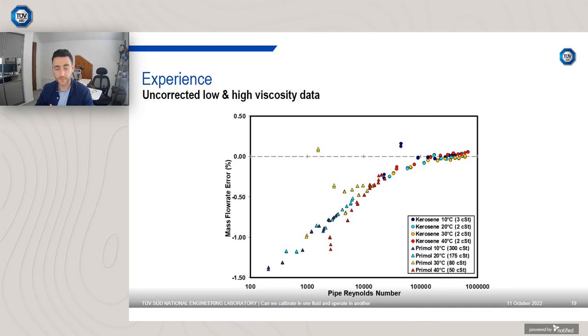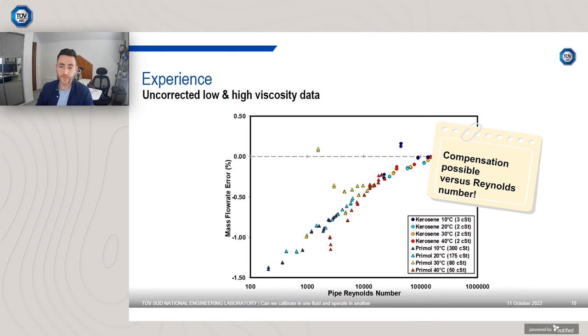So Coriolis meters can be compensated with respect to Reynolds number. If you can infer Reynolds number, you can potentially compensate for it. And there are some Coriolis meters that are now using this kind of methodology. They have it embedded within their flow computer or their transmitter for the calculations.